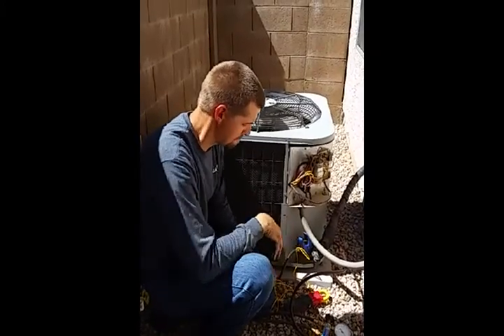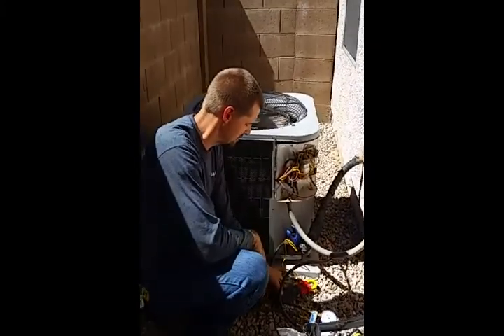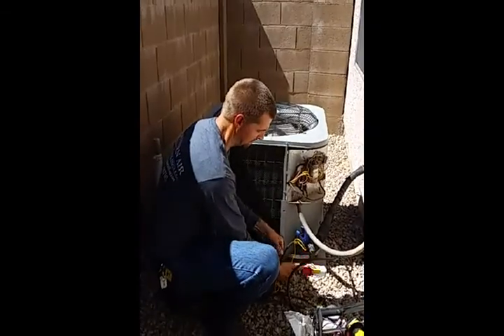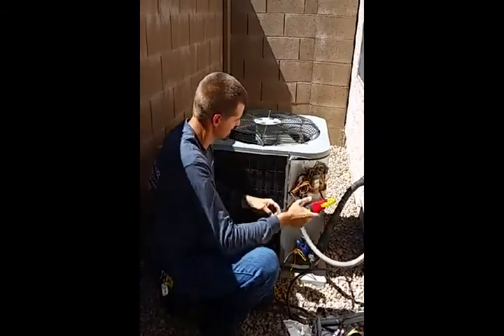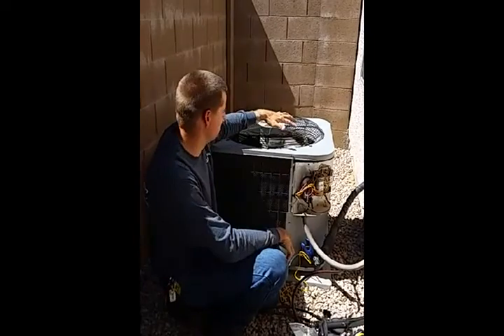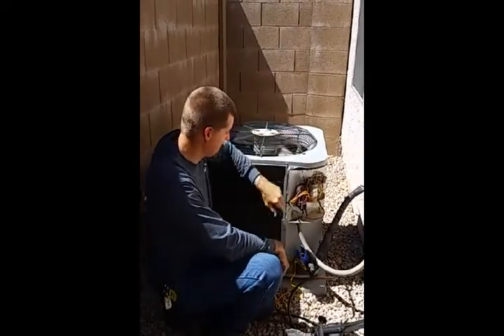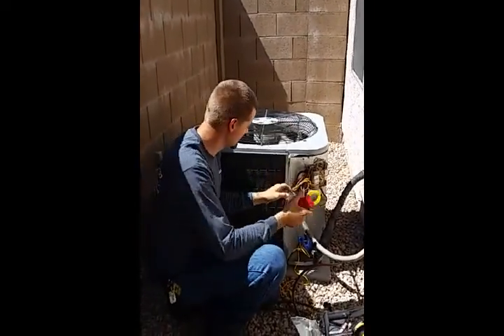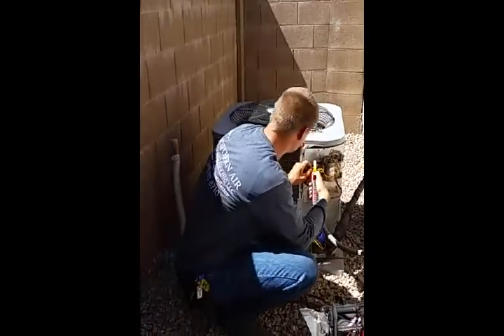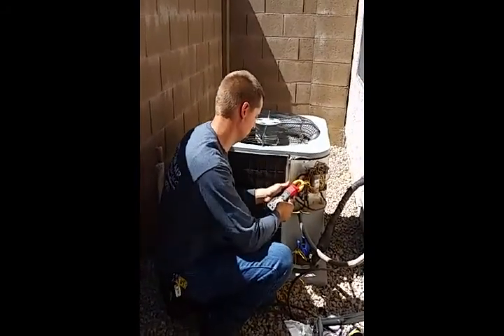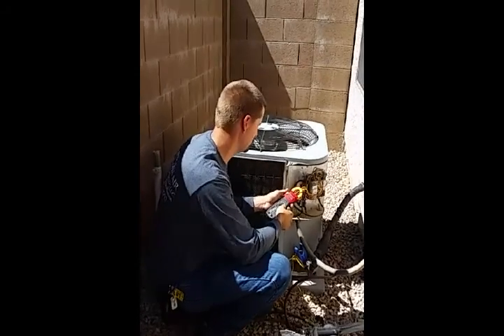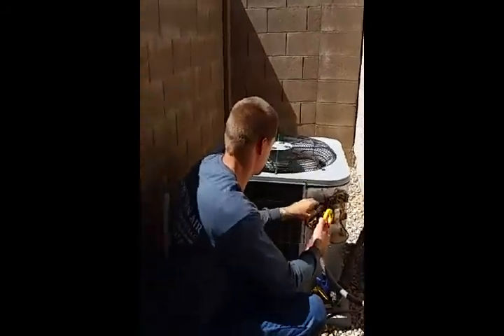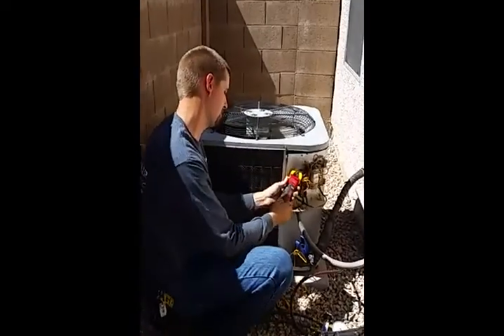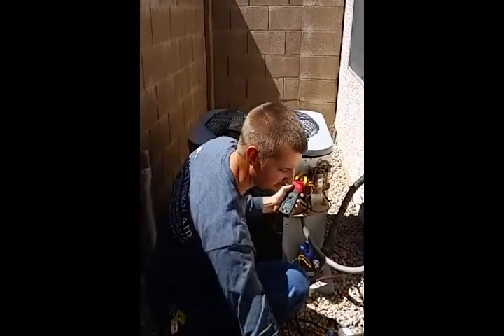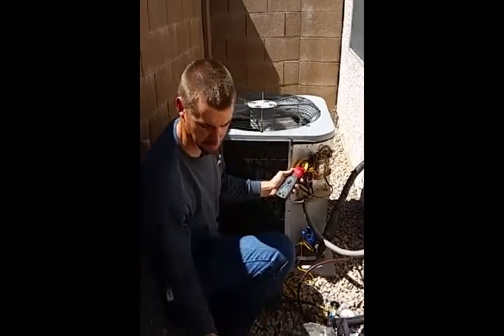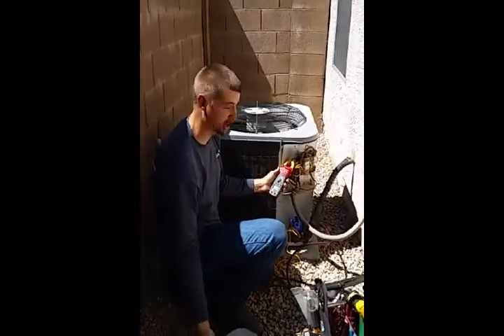Okay, the next step would be to go ahead and pull this off here and check the amps. Okay, now the amps of the fan motor itself, and then the compressor. Okay. Good. And we're okay. We're okay on both. So.